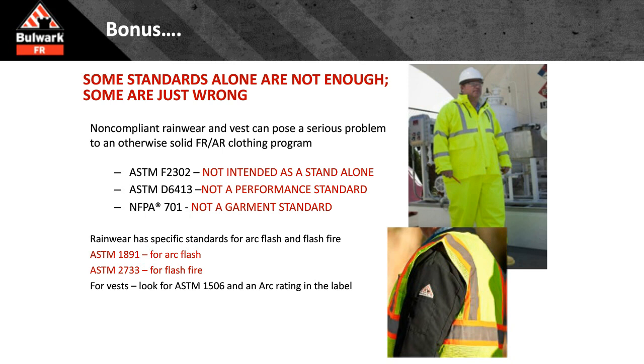Example, ASTM 2302 was removed until they reconfigured it to reference it's not a standalone standard in and of itself to tell you enough information of whether or not it will work in the hazard. Why? The marketplace was abusing that and creating flame-resistant and marketing flame-resistant vests and rain gear to meet 2302. 2302 is just a heat-resistant, flame-resistant standard, and if you read it, it says not to be used in arc flash or flash fire.